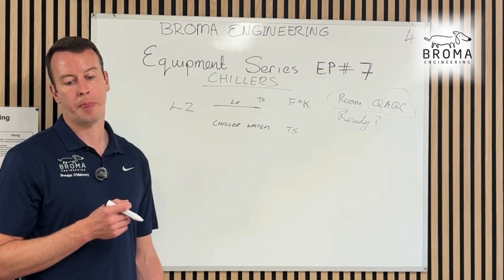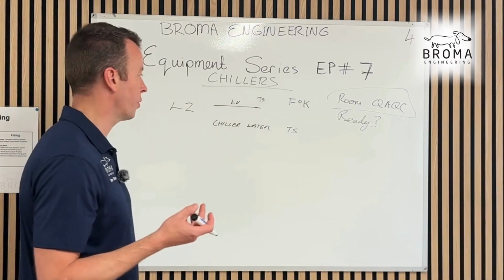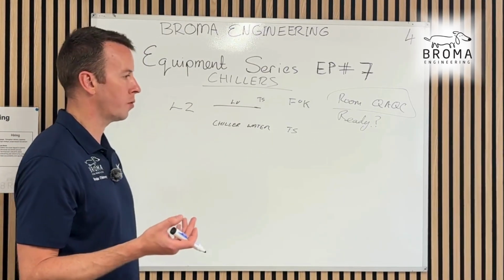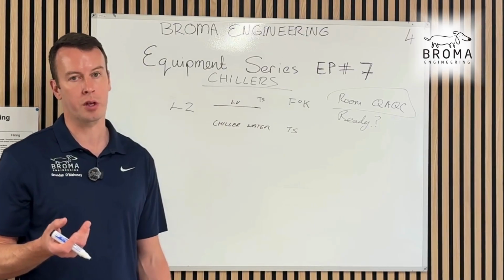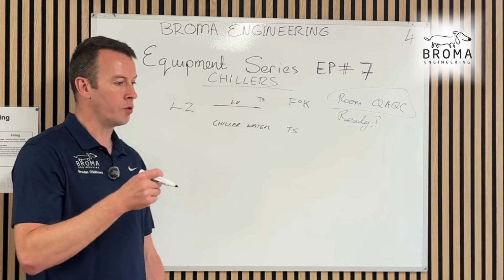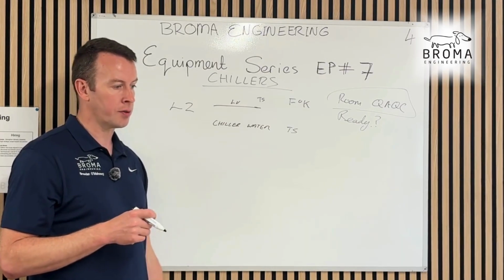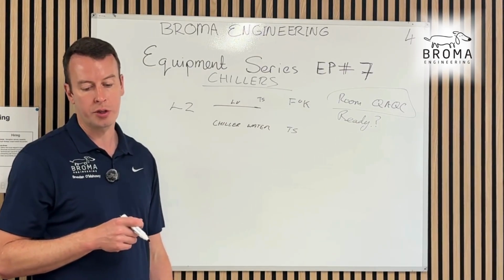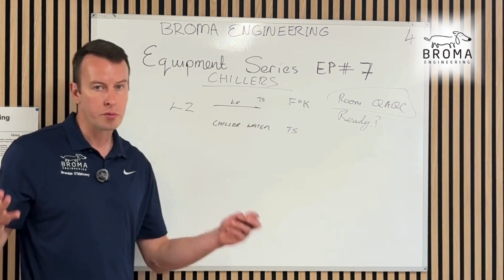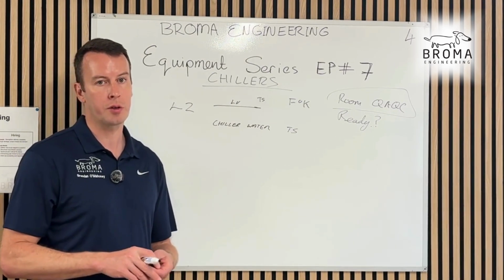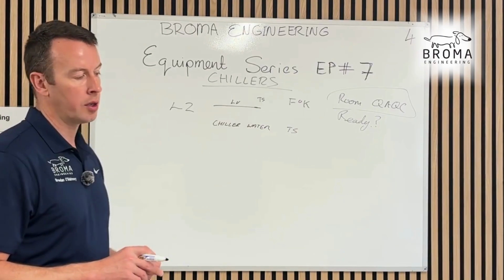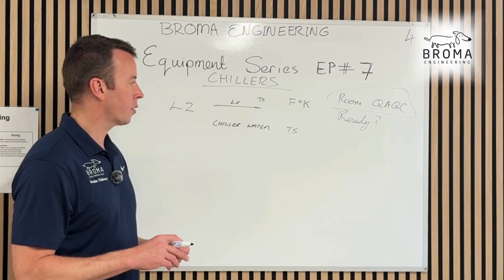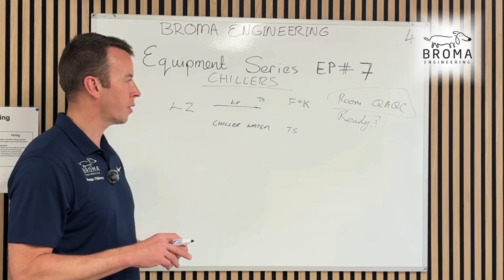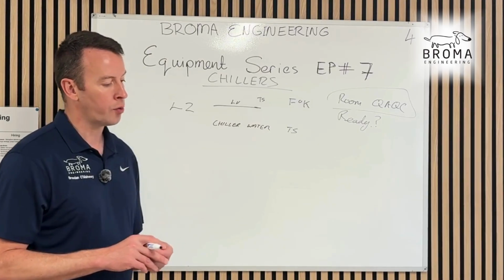So your stab-in points, positions, do they make sense? Are they accessible? Can people see them? The valve positions, can we move the valves, actuate the valves? Are they accessible? Can operations get there? Do they need a hop-up? Etc, etc, etc, that's all part of the design review. And sometimes this is very late because pipework takes a long time before the design is ready for pipework to be designed.